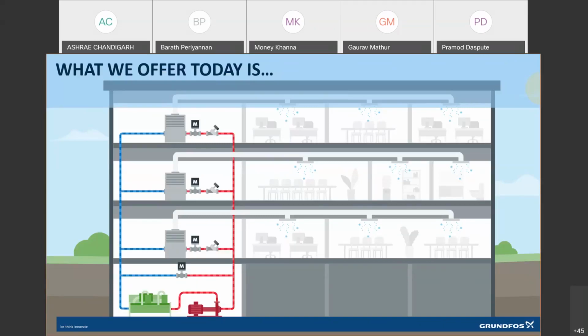Now, this picture shows what is currently happening in terms of the designs which are possible today. I have made today's design in a very small picture, but it has various forms available: a primary-secondary chilled water pumping system, or a variable primary chilled water pumping system. For the purpose of our discussion, I have taken a variable primary chilled water design, where you have a set of pumps pumping water through the chiller evaporator coil, and from those pumps the chilled water is pumped to the entire circuit. I have simplified the design for ease of understanding, but of course there are many complex dimensions to it.